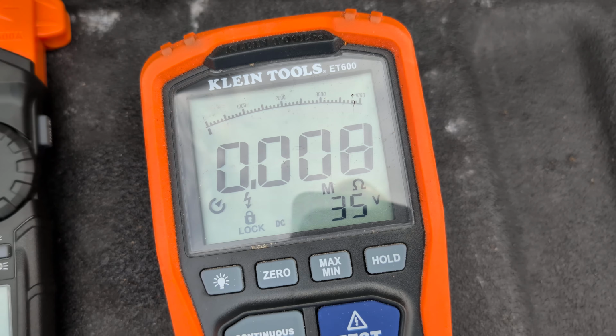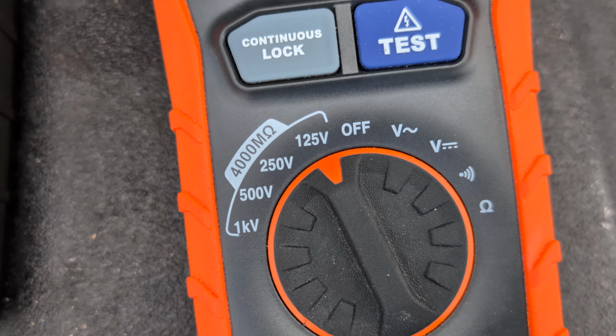If you have 24,000 ohms or less on a 120 volt circuit, you're going to draw more than 5 milliamps. So if you draw more than 5 milliamps, you're going to trip a normal GFI device. And this one's only 8,000 ohms at 125 volts.